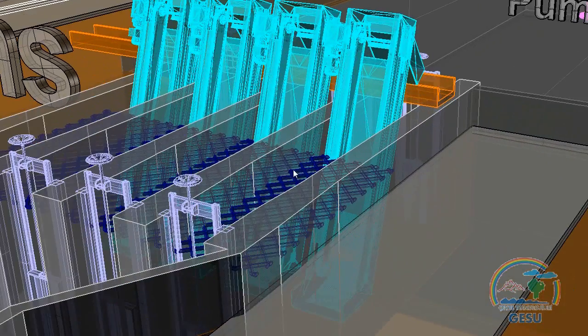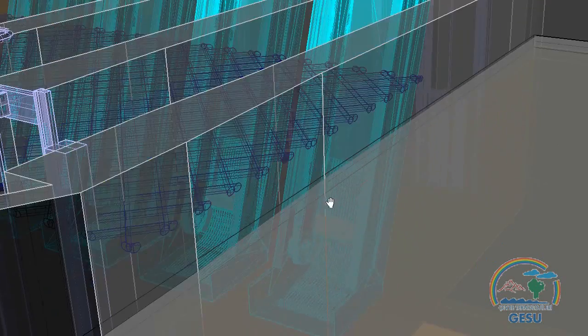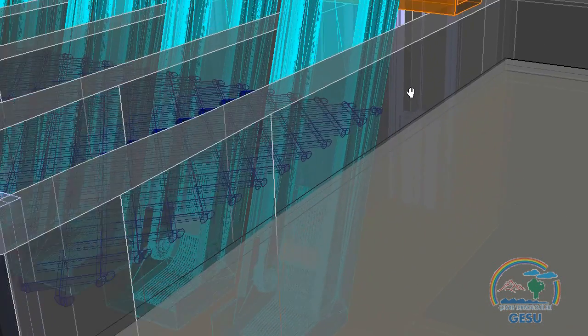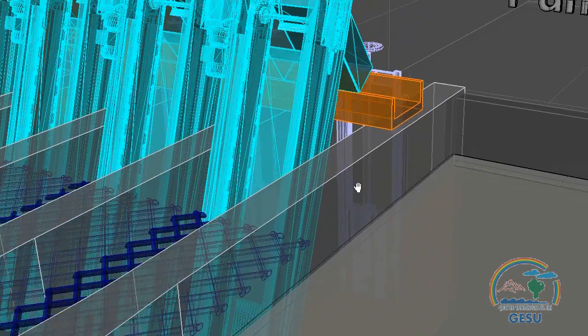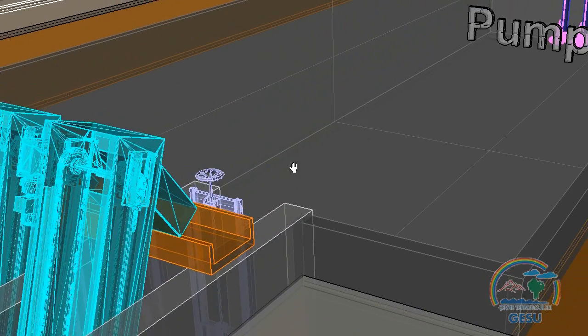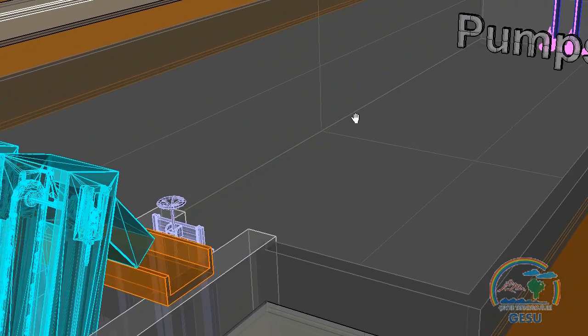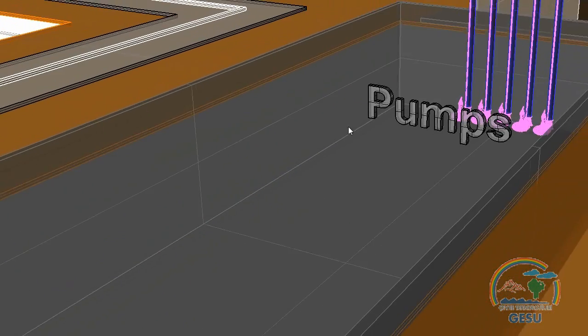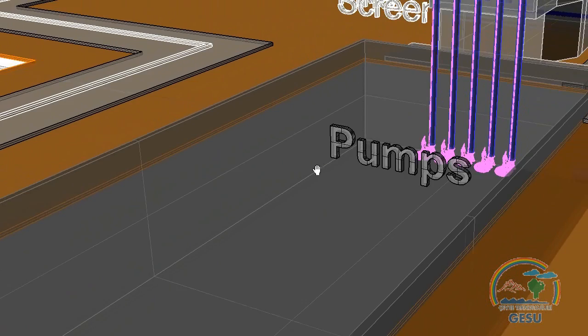Water passes through penstocks and comes to the coarse screen unit. In the coarse screen unit, there are 4 screens, each with 5 cm bar openings. Large particles are captured in this unit and water continues to the inlet pump station.